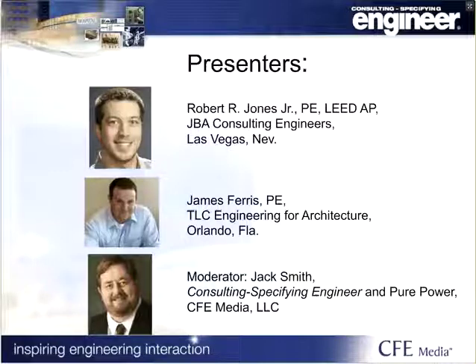Thanks, Jim. Rob, can the ATS be in the same room as the generator? Yes. NFPA 110 allows the ATS, which is part of the EPSS, to be located in the same room as the EPS, the generator. I think earlier in the slides we had a code reference for that. And that would also apply to the parallel switchgear.